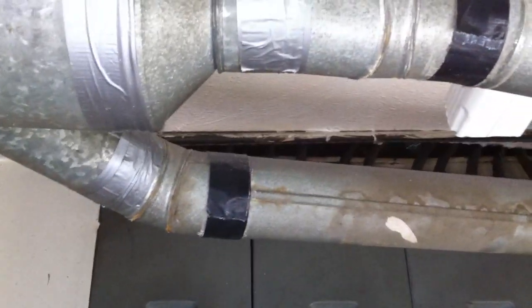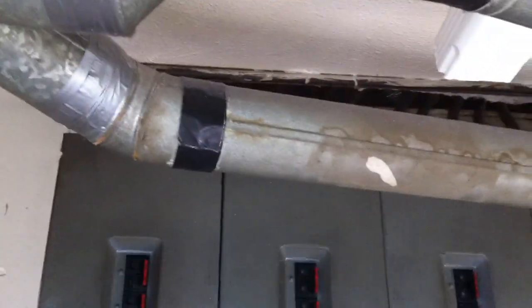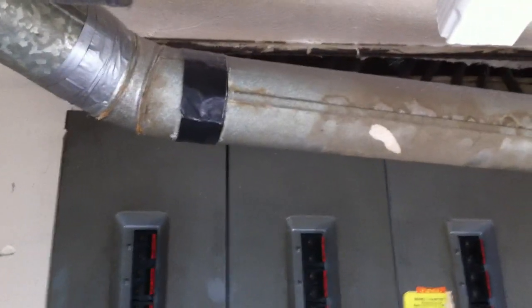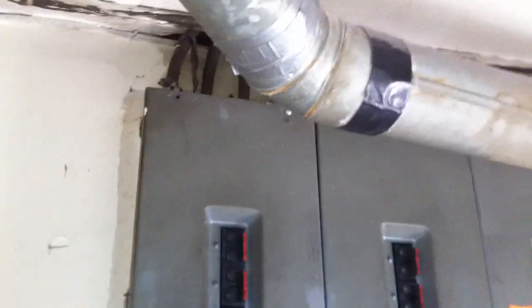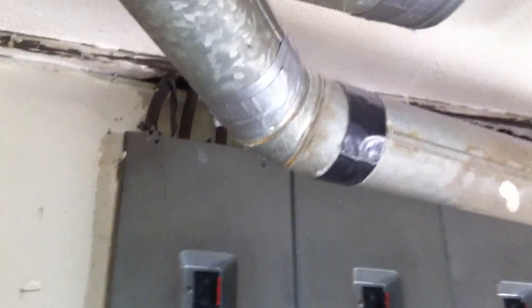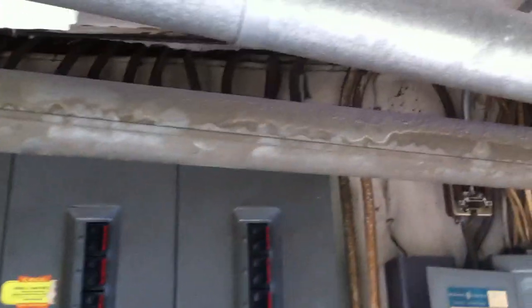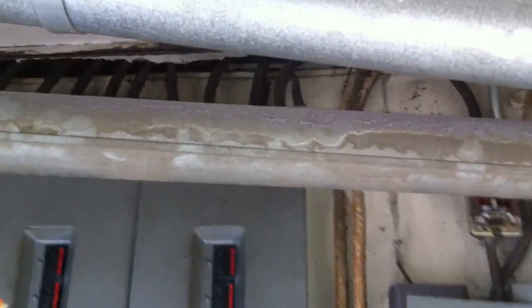With the way this piping is positioned, you certainly can't open it 90 degrees. And then as we look up, we'll see there's no headroom. The headroom, according to 110.26A3, has to be at least as high as the equipment, 6.5 feet minimum, or at least as high as the equipment. But as you can see, this ductwork is right in the way.